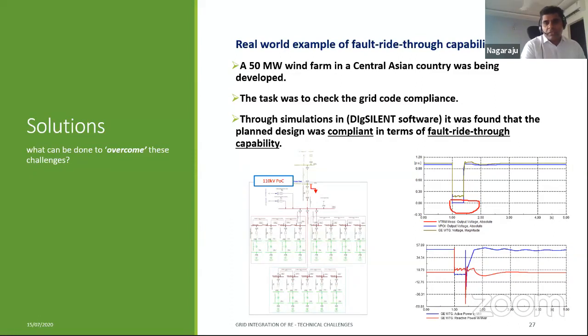And we found that the wind farm is marginally stable. You can see the oscillations. The top picture shows the voltage dipping to 0 for 650 milliseconds, whereas the bottom picture shows the real power output in blue and the reactive power output in red. After the disturbance, the machine is coming back to its original state, blue back to blue, red back to red. But you will see a lot of oscillations in the real power.